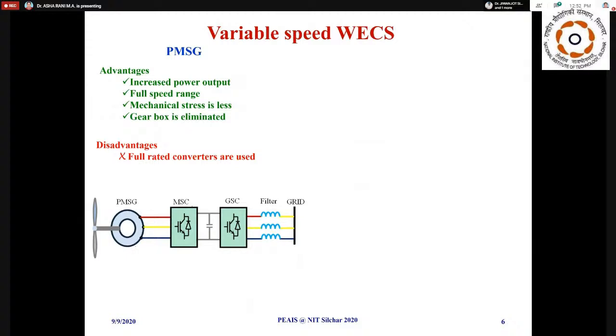One more thing is that the flux produced inside the PMSG is not a very pure sinusoidal shape, it is trapezoidal. So the role of this converter becomes a little bigger, because it first has to make it a proper sinusoidal shape, since only then can you integrate with the grid. You cannot pump any power or current to the grid if it doesn't have a proper sinusoidal shape, because doing so would introduce a lot of harmonics into the grid.